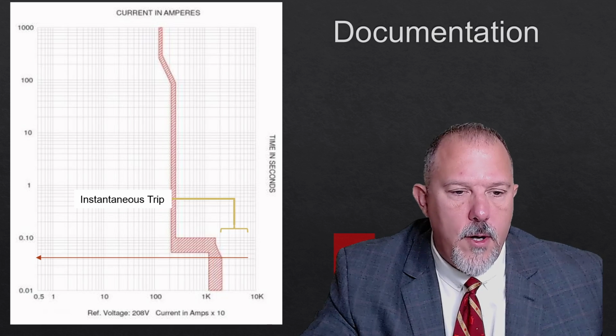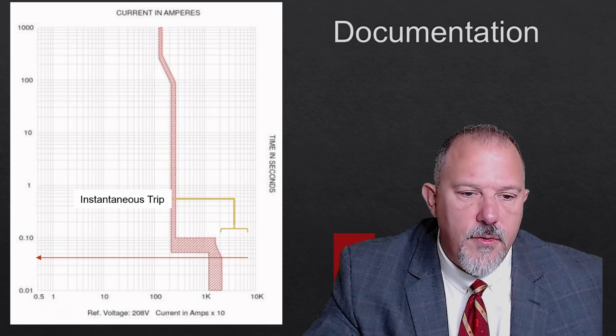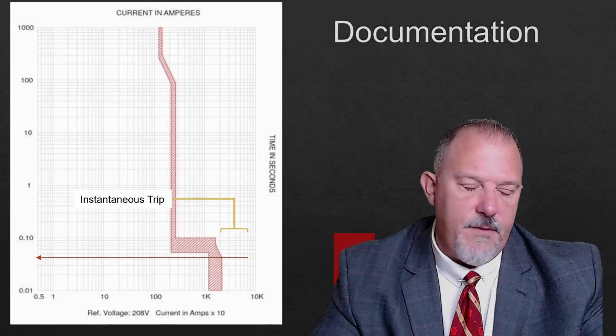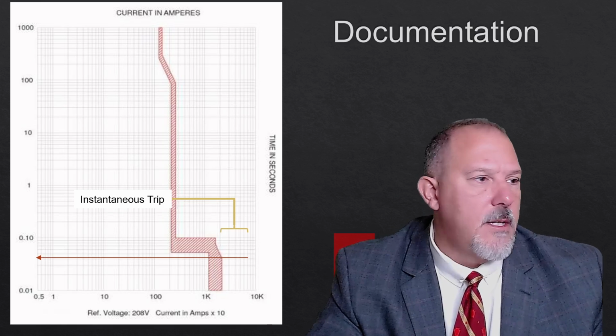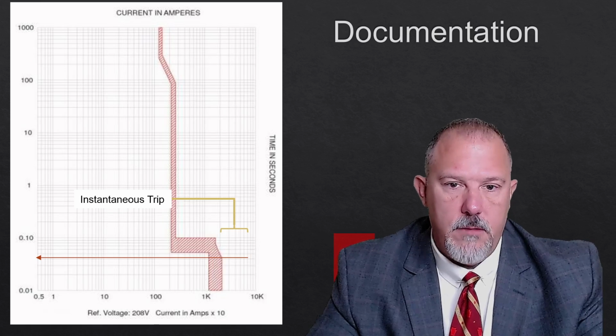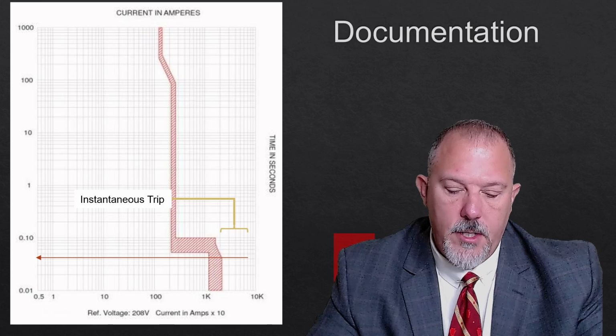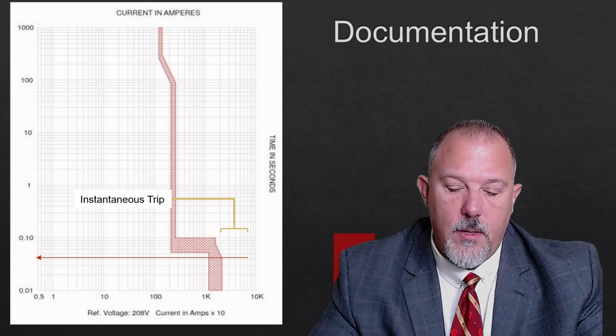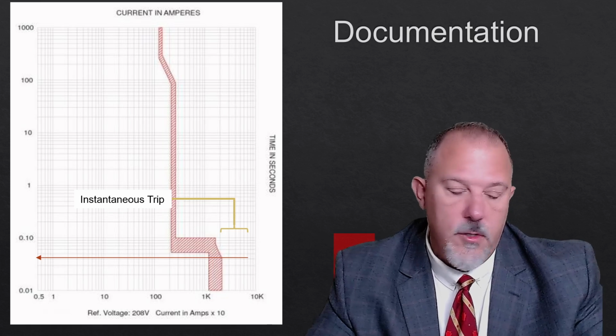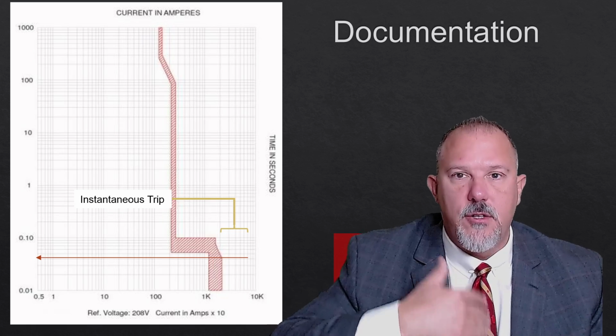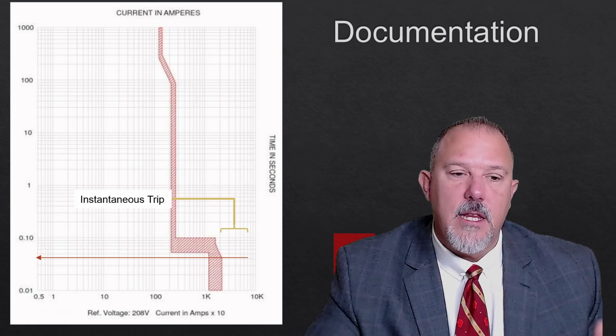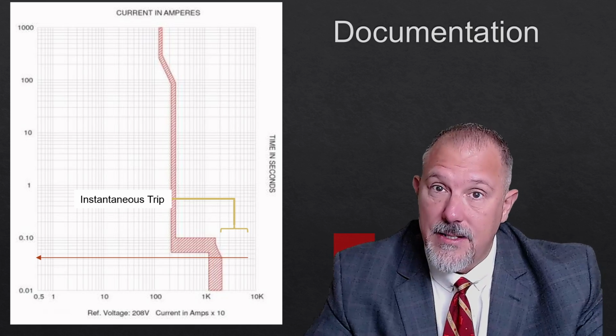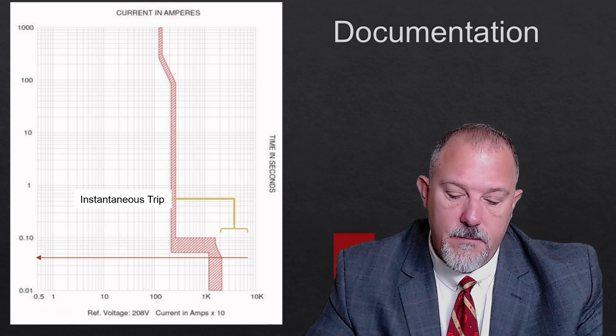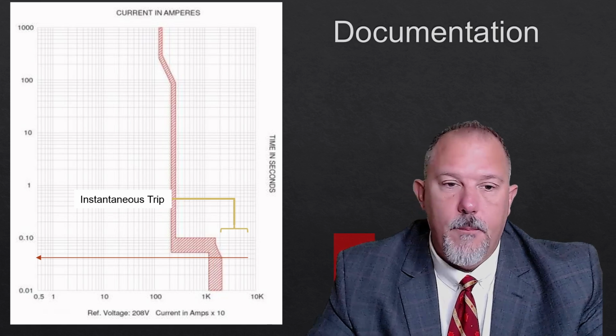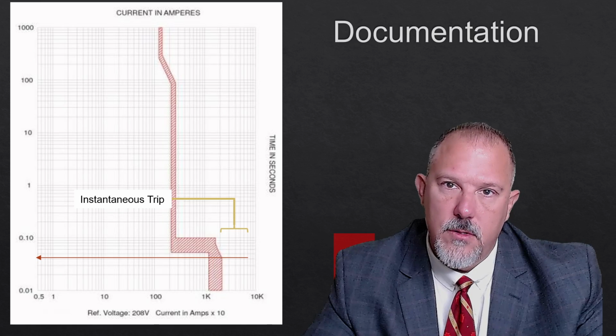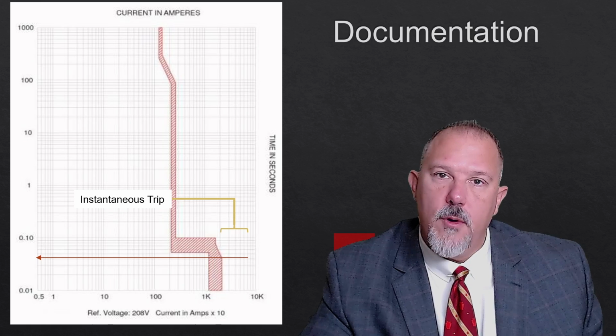That clearing time is 0.01, 0.02, 0.03, I don't know, we'll call it 0.035, 0.036. We'll call it 0.036, all right? 0.036 divided by 0.016 is 2.25 cycles. So I can take a fault and reduce that down to 2.25 cycles with this device. If I can get this to clear at 0.01 seconds, where 0.016 is one cycle, 0.01 seconds is 0.625 cycles. So it's less than a cycle, a little bit more than a half cycle.